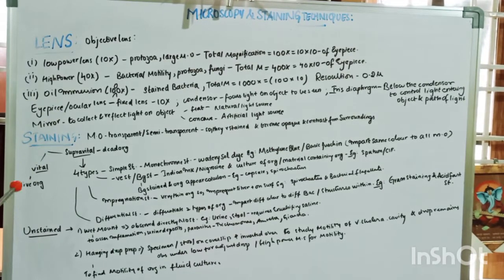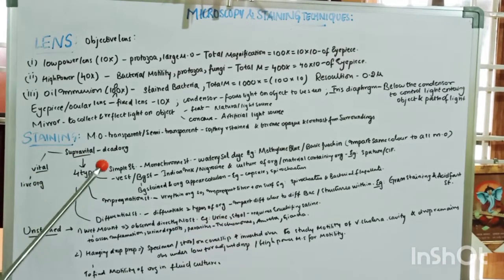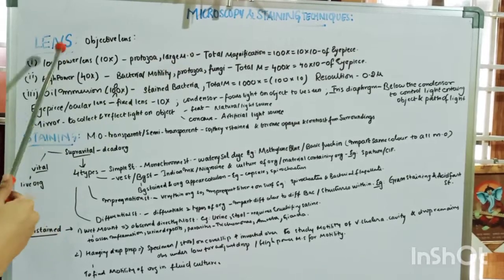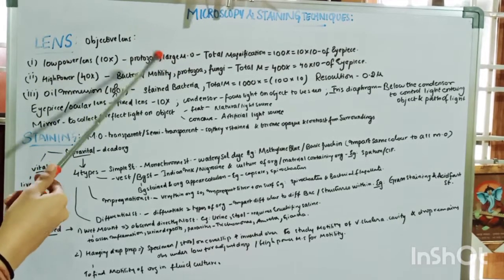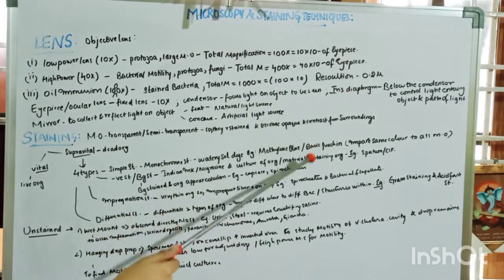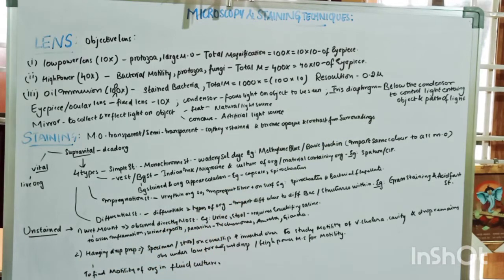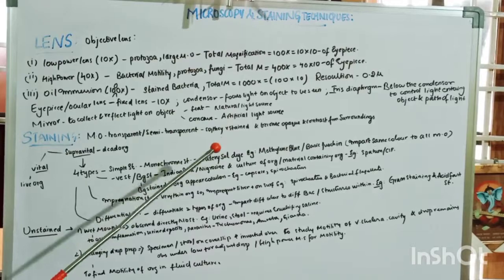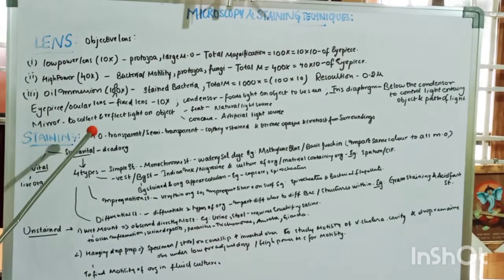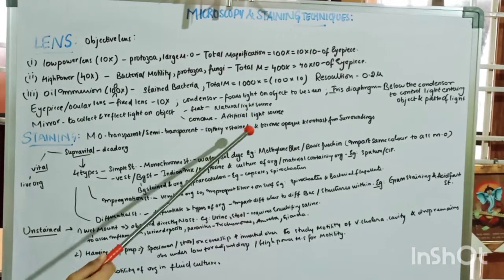The eyepiece or ocular lens is a fixed lens — we cannot move it, but the objective lenses are interchangeable depending on the organism size. The condenser focuses the light on the object to be seen. The iris diaphragm is just below the condenser and controls and regulates the path of light entering the object. The mirror collects and reflects light onto the object; it may be flat for natural light sources or concave for artificial light sources. Nowadays, a direct bulb light source is used instead of a mirror.